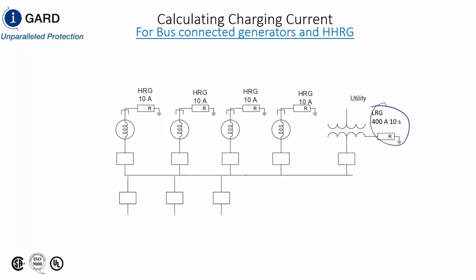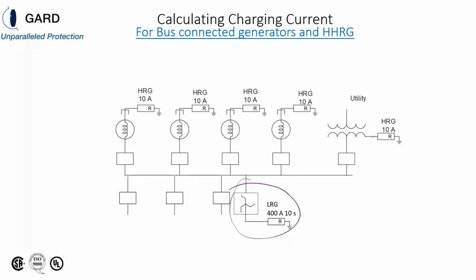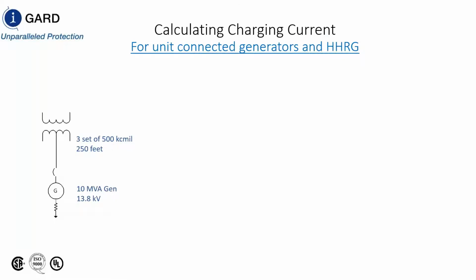So when people come to I-Gard and ask for a hybrid high resistance grounded system, we always ask for the methodology of the generators being online. If they're going to island, you have to have enough ground return current for that island condition. For example, like this, you would have to have a ground return path on the bus. And the reason why that's important is because we have to have enough current to measure the charging current or to overcome the charging current of the system.